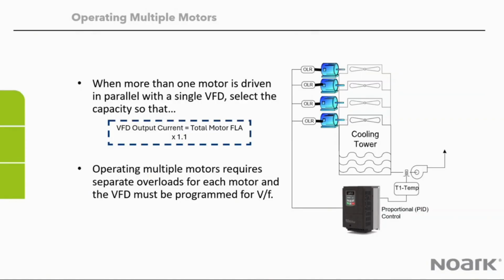Include separate overload modules for each one, and then program the drive for voltage frequency control. So you can see here we've got a temperature transmitter into a PID loop inside the drive, and that would be varying the speed of the fan based on the temperature input.